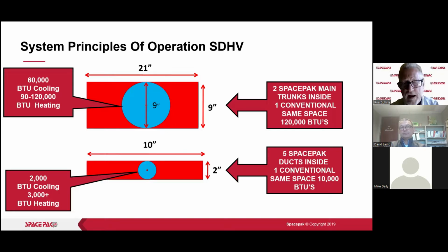There's an inherent energy efficiency right there: we have less duct area, so less heat leakage or heat absorption through our duct surface. On the 2-inch tubing, on a 2 1/4 by 10 duct wall stack, for instance, we can fit 5 of our 2-inch ducts, which is equivalent to about 10,000 BTUs. So we've got 2,000 BTUs in cooling versus 10,000 BTUs in the same space.